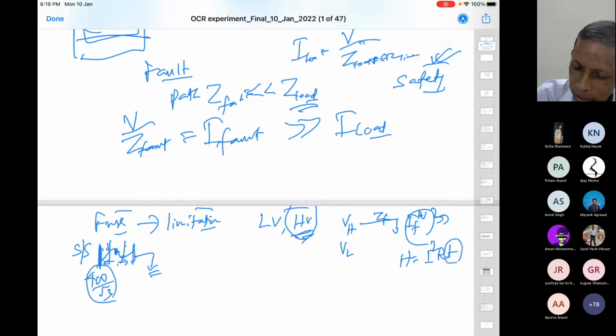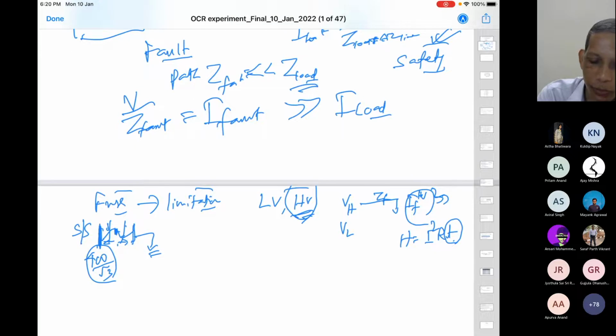So therefore in a high voltage system, the time left for us will be substantially low and small to avoid possible damage. To evade possible damage, the time which will be allowed to planners or designers is much smaller in case of a high voltage system compared to a low voltage system, because the possible damage may be detrimental at smaller times also. So in a typical time frame, in a low voltage system, we talk in terms of seconds or fractions of a second, and in a high voltage system, we talk also in terms of milliseconds. That is the system protection requirement. So that is about that. So if you find a limitation, then what?